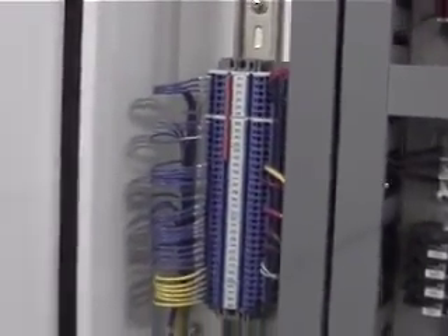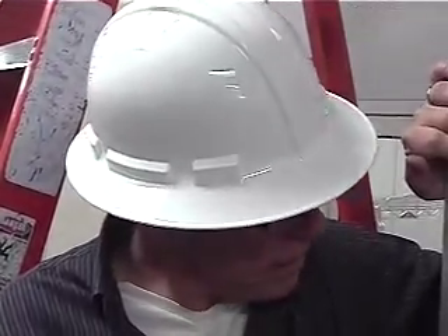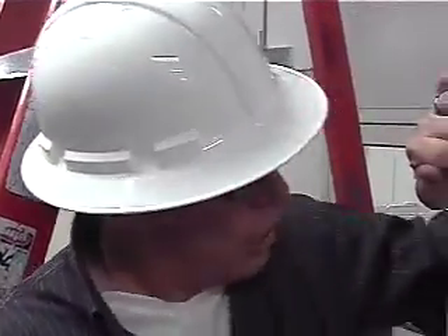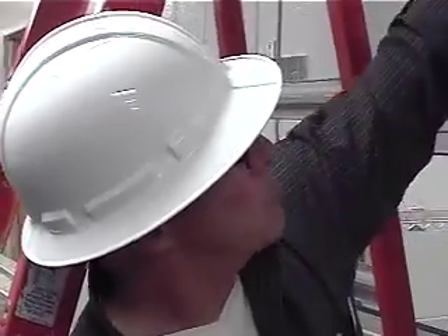We talked about the RTDs. We should get into that real quickly. We have 2 RTDs in the room. There's one directly in front of the room, and I think one installed inside the coil itself. So what is the RTD? The resistive temperature device. It's a fancy name for a little platinum resistor that tells you what the temperature is, and they're kind of the industry standard. It's a 100 ohm RTD, just little 3-inch encapsulated temperature sensors. One is directly on the other side of the wall here, and then there's one inside the coil.